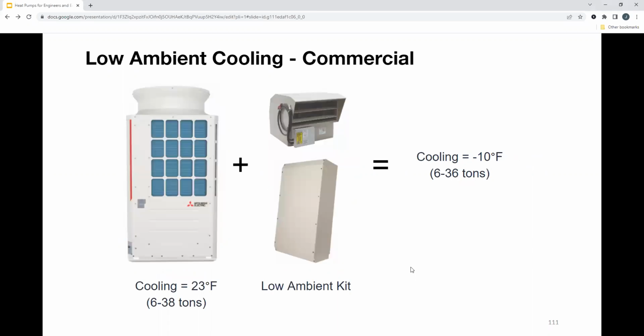And then if you do have a bunch of server rooms, electrical rooms, all next to each other, stacked on top of each other, you can get into the commercial heat pump world and basically lock out the heating operations so this stays in cooling year round. In order to extend those cooling lengths, you basically need to add a low ambient kit on, which is wind baffles and a motorized hood. And that will give you 100% cooling capacity down to negative 10 degrees if you are looking to provide cooling year round. So those are just low ambient cooling applications. We do them quite a bit. This is an option, whether it be split or commercial.